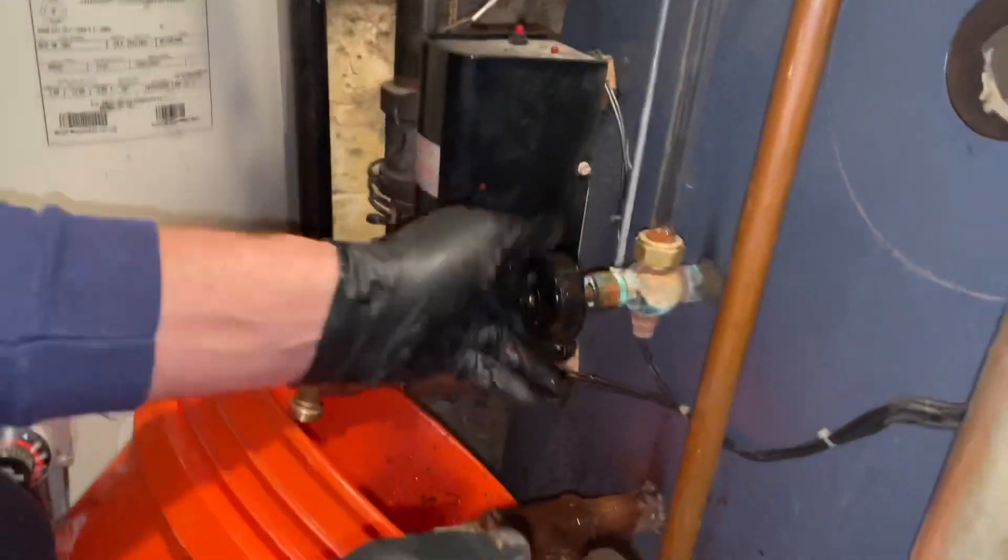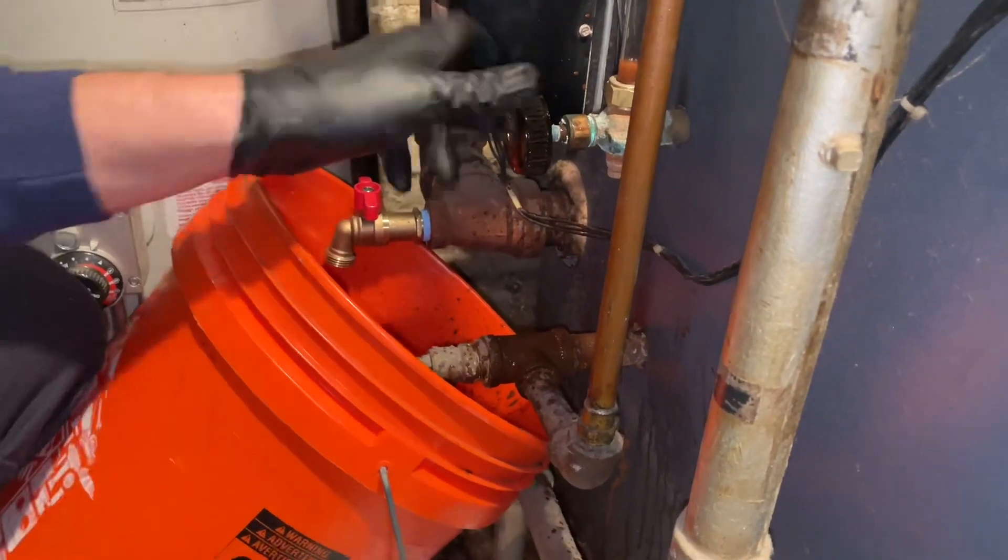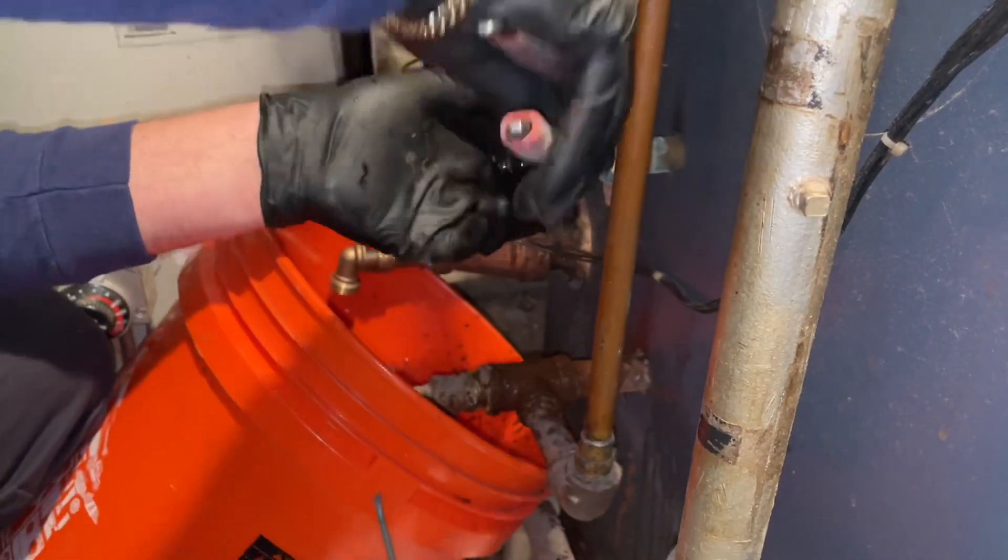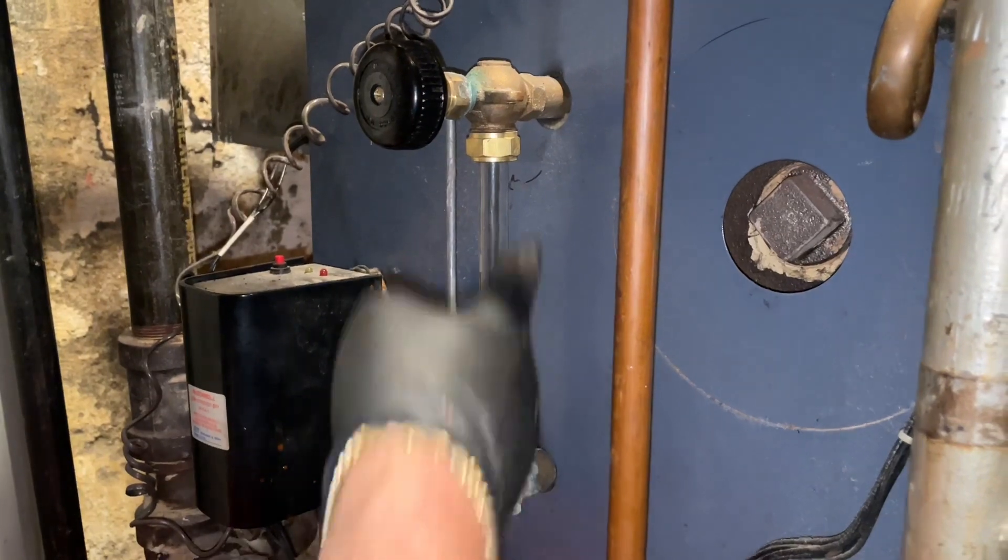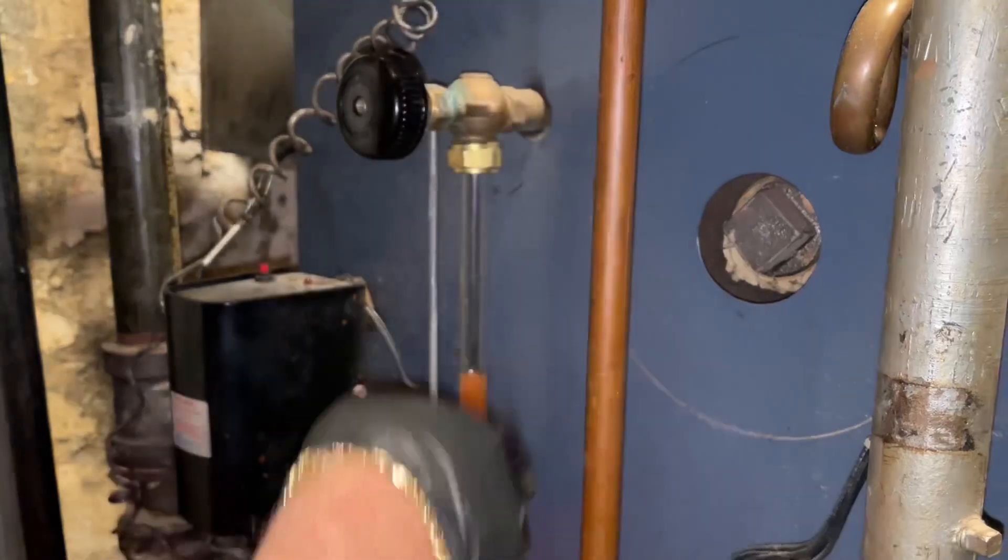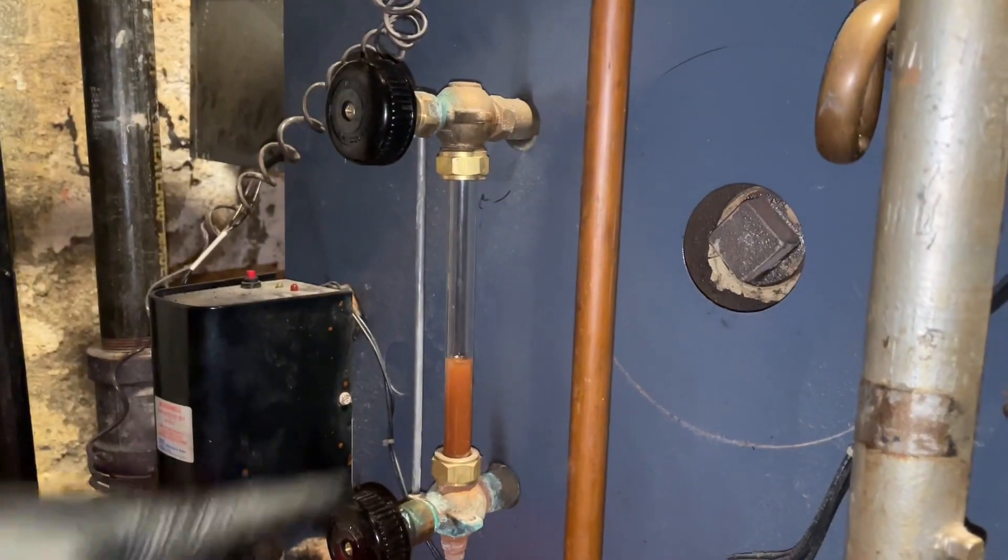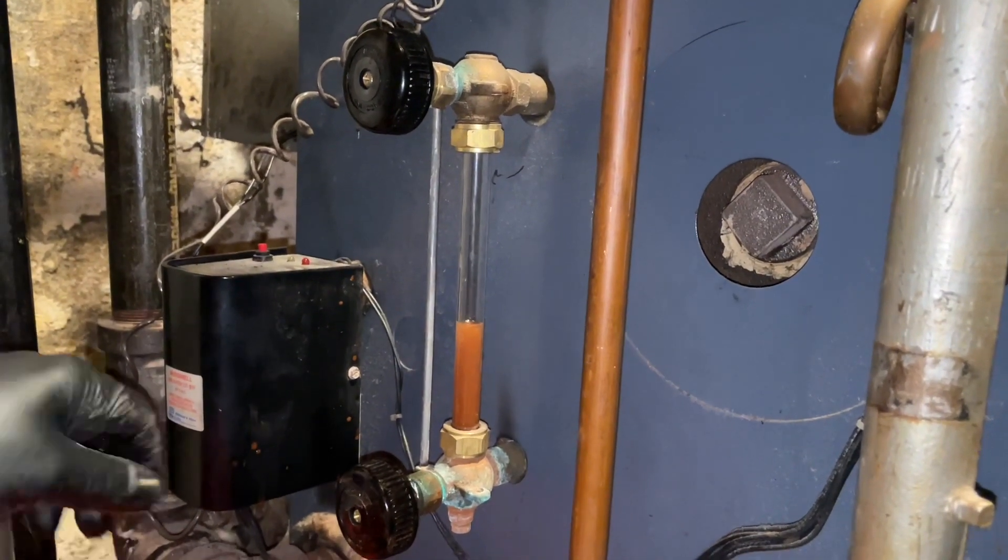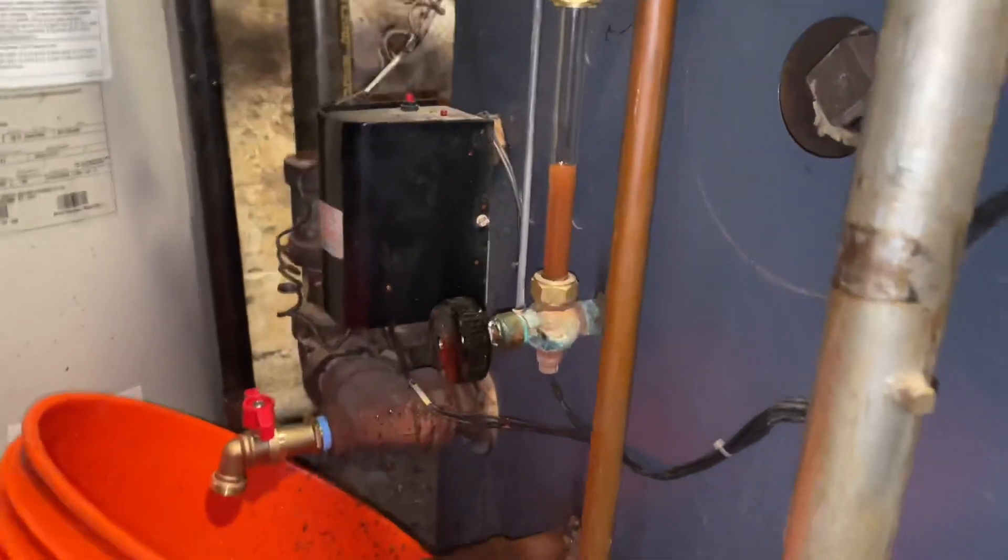Should really give this one some steam boiler treatment. So if these are clogged, if this is clogged and that's clogged down there, you won't have a good sense. You won't have any sense of what the water level is in the boiler. And let's say this one up here is clogged and this one down here isn't, it won't go up because you need equal balance, the water balance pressure. That's why there's an upper and lower valve. So we're going to fill this one up a little bit, drain this one down. She hasn't been serviced since last year and I doubt anyone is draining the boiler.